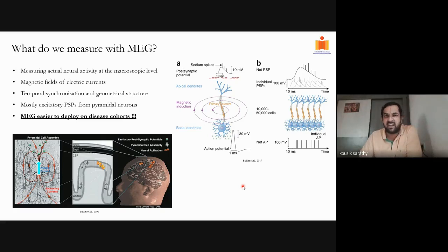MEG has a slightly different way to measure the magnetic fields compared to EEG. With EEG, you just put 2 electrodes on the scalp and you are picking up the potential difference. With MEG, because of the size of the potential, the energy that you're trying to pick up, and also other interferences that might come in, the setup is slightly more complicated. It's a cryogenic device. The pickup coil is actually dipped in liquid helium, so that you are in superconducting states to pick up these signals.